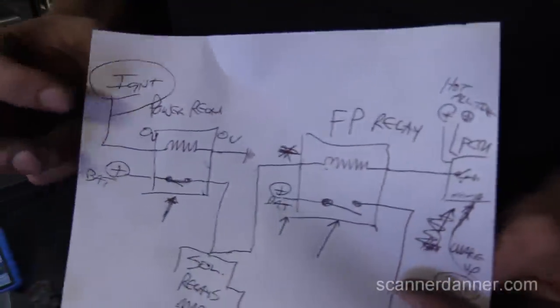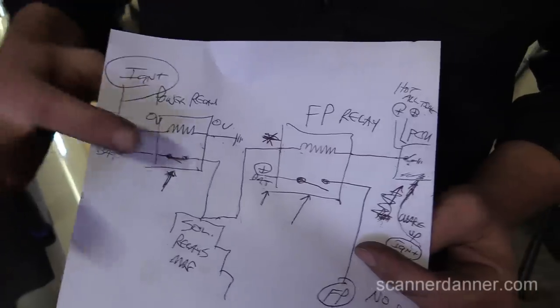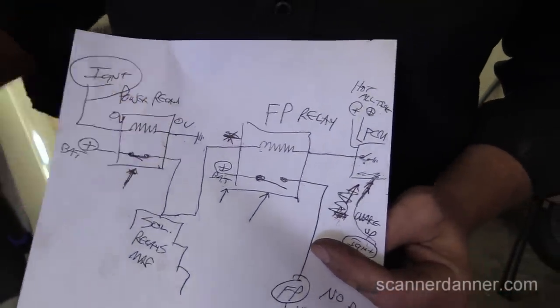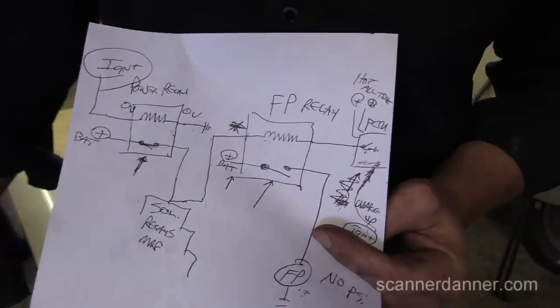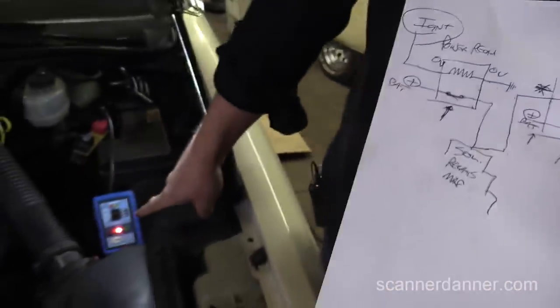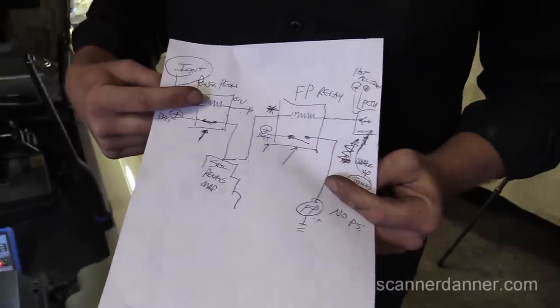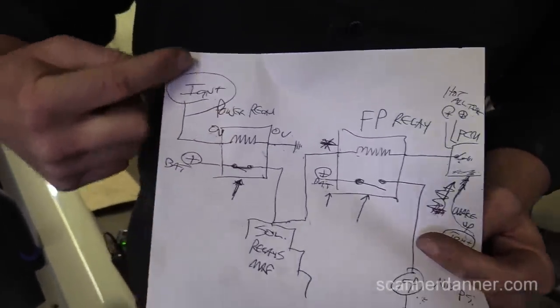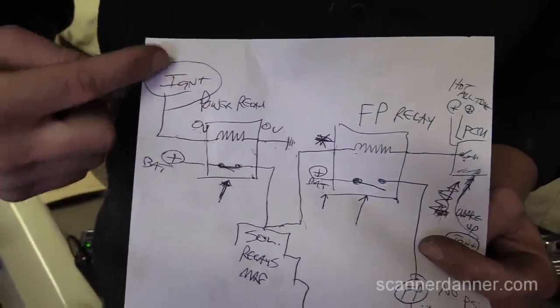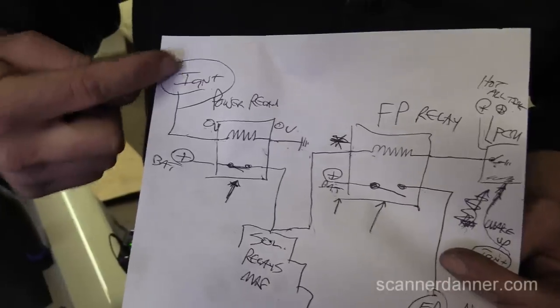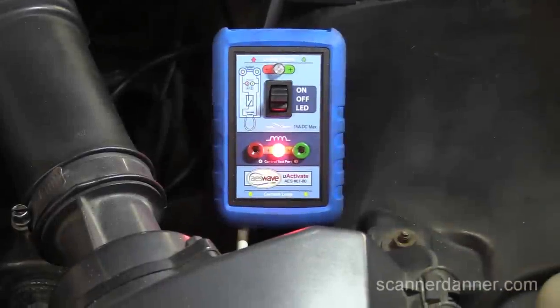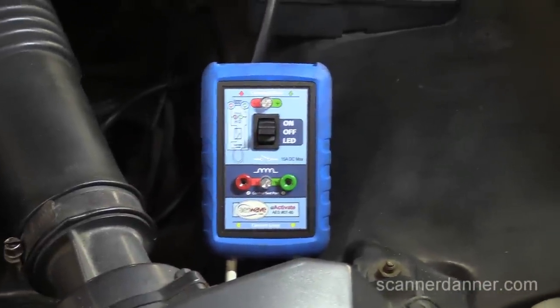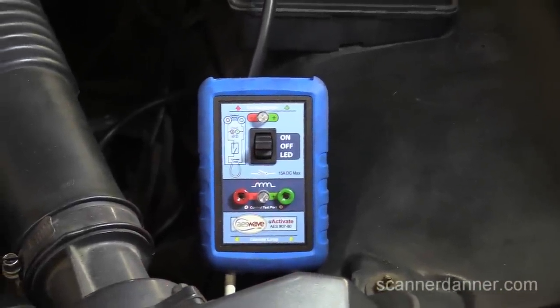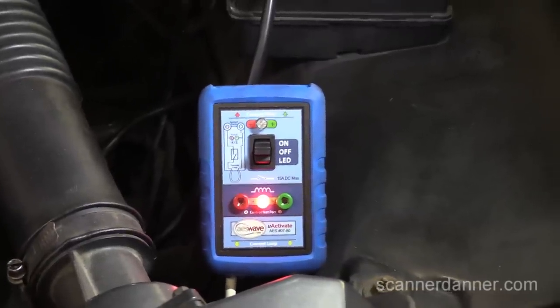So look here. What we just fixed is the power relay control side, that coil that's lit right down there is this coil here. And the power feed, this was the blown fuse right here. The fuse, I'm not drawing it in the picture. When I pull that fuse back out, you're gonna see that light go off. Watch, stay focused there. That's fuse out. That's fuse back in.